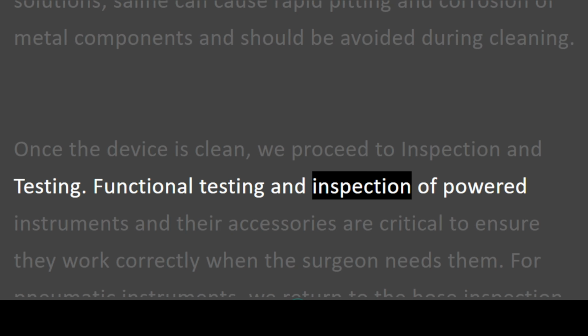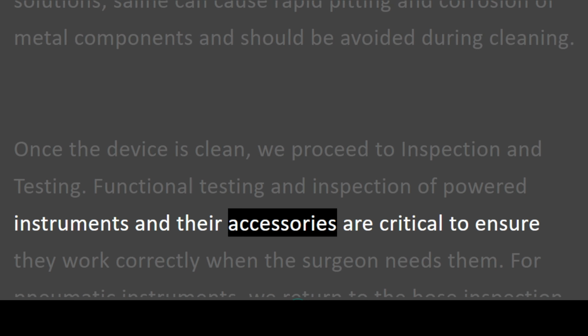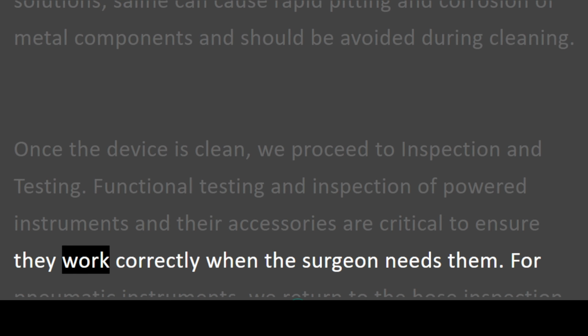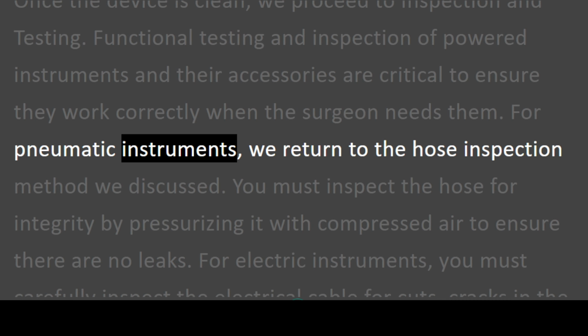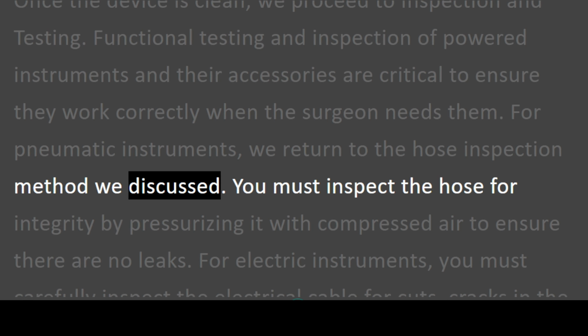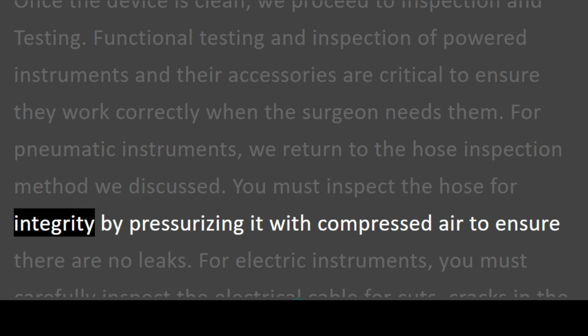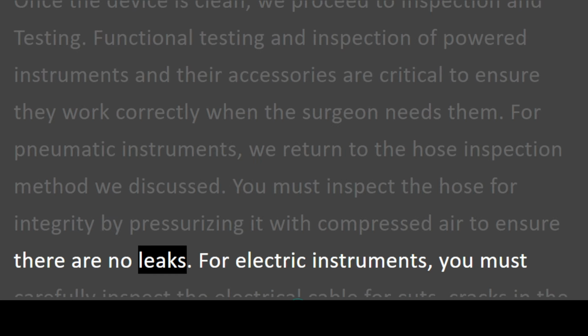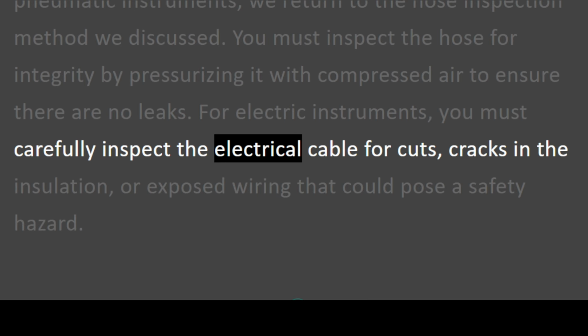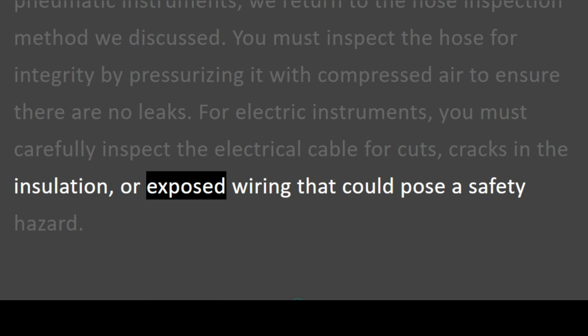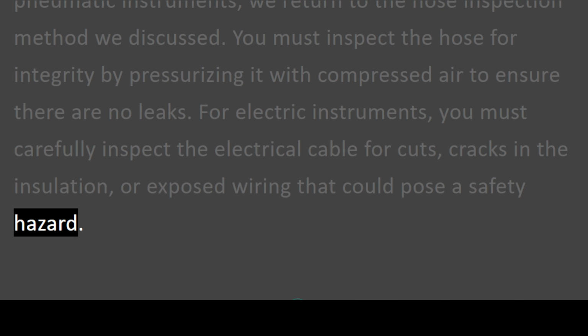Functional testing and inspection of powered instruments and their accessories are critical to ensure they work correctly when the surgeon needs them. For pneumatic instruments, we return to the hose inspection method we discussed. You must inspect the hose for integrity by pressurizing it with compressed air to ensure there are no leaks. For electric instruments, you must carefully inspect the electrical cable for cuts, cracks in the insulation, or exposed wiring that could pose a safety hazard.